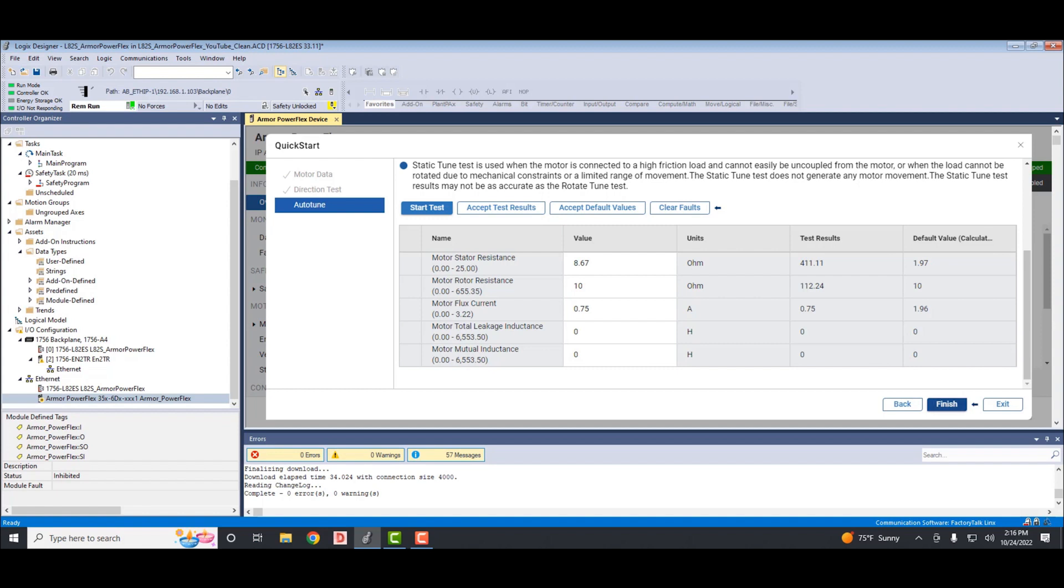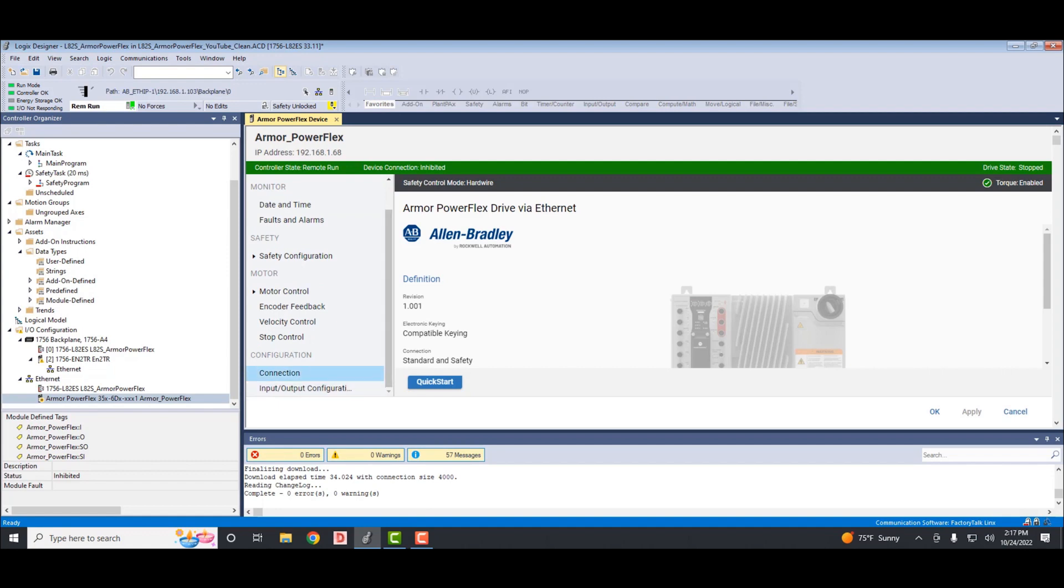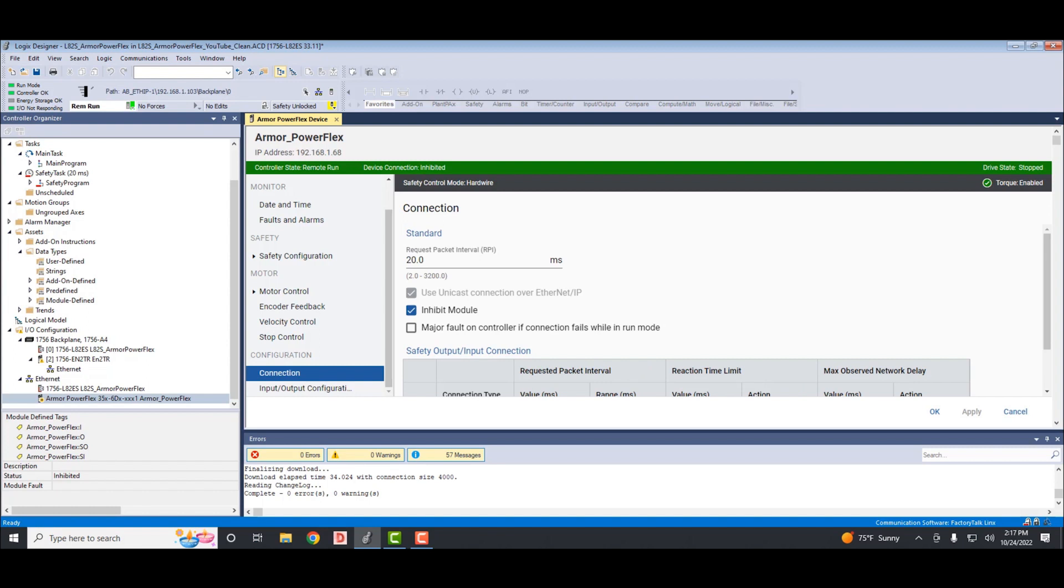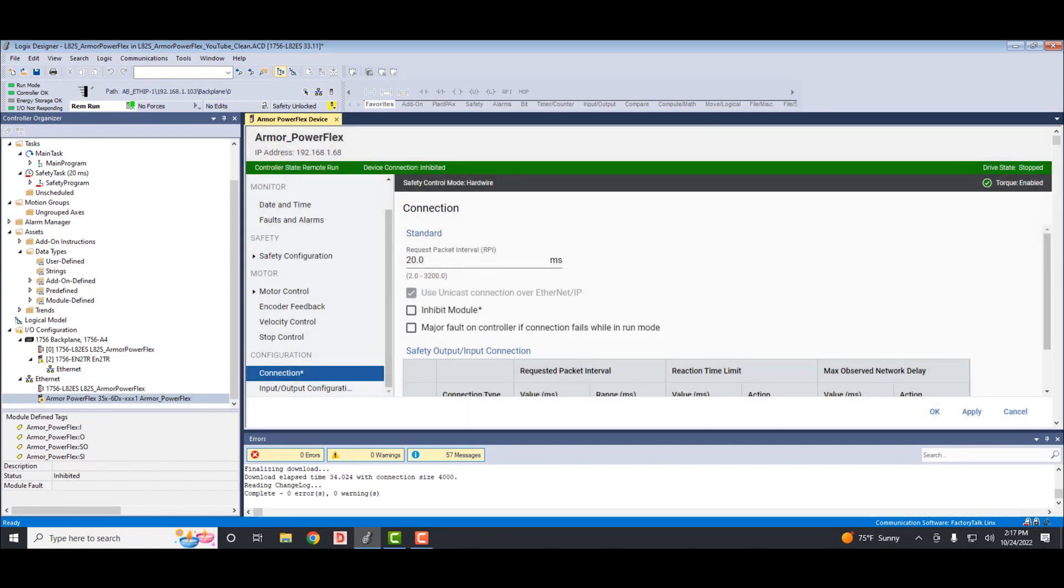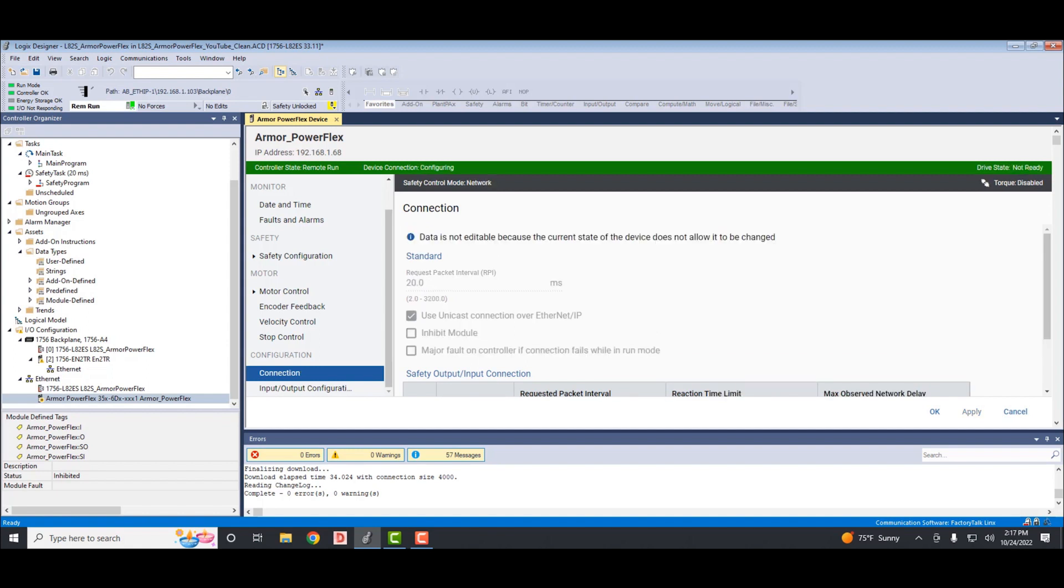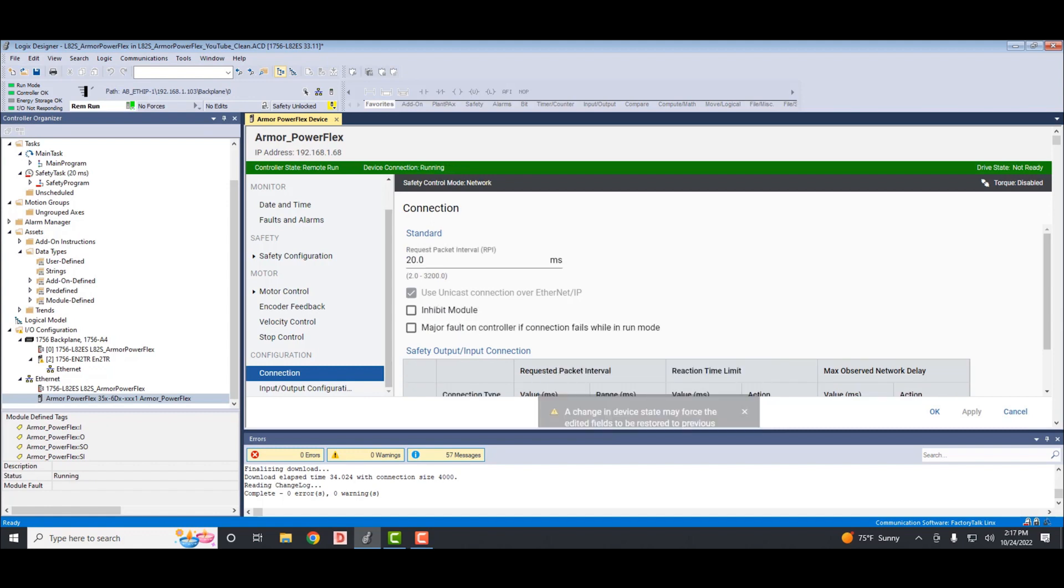Go to the connection tab, unselect the inhibit module box. Now apply at the bottom of the tab. Once this is applied, the drive will now go back to network safety configuration. You'll see it right up here. It'll change from hardware to network. And at this point, you can remove the red safety jumper from the safety input.